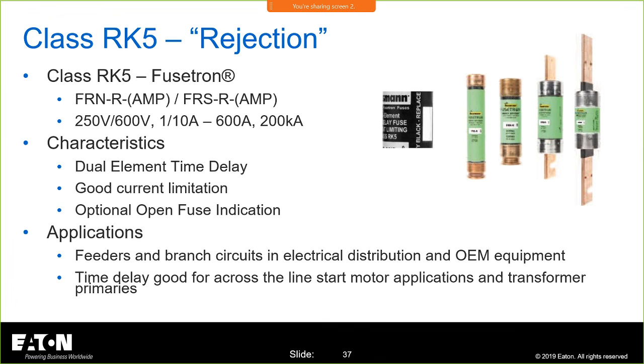Dual element time delay, good current limitation, optional fuse indication. So there's a lot of different options, you can tell when these fuses have given their life to protect whatever it is that they're there to protect. Feeders and branch circuits, you'll see these on feeders and branch circuits. Again, for motor applications, transformer primaries, green is good.